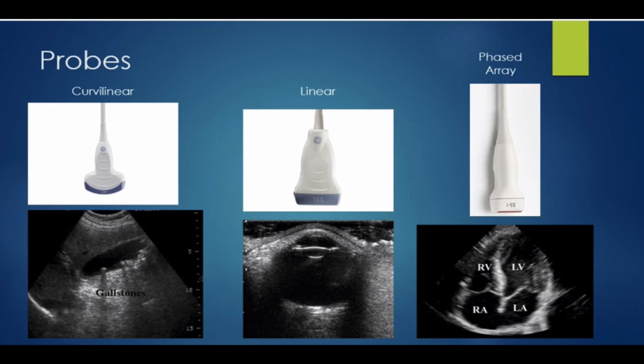There are a number of different ultrasound probes; here are three of the most commonly used. The curvilinear probe is used to image deep structures, often within the abdomen. The probe uses sound waves of a lower frequency, which will travel further and penetrate deeper within the abdominal structures. However, this sacrifices some resolution of the image. Here we can see that the curvilinear abdominal probe is used to look at a gallbladder, and we can even visualize small stones within the gallbladder.